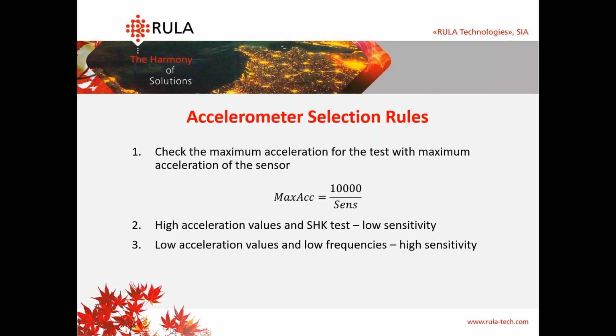For regular tests, I recommend using accelerometers with sensitivity of 10 or 100 millivolts per G. But if you're running a shock test with high acceleration values, you need to use sensors with low sensitivity, like 0.1 millivolt per G. And if you run tests with low frequencies, low accelerations, it's better to use high sensitivity sensors like 1000 millivolts per G. You should remember that sensor selection is really important, and this will help you not to get an overrange channel.